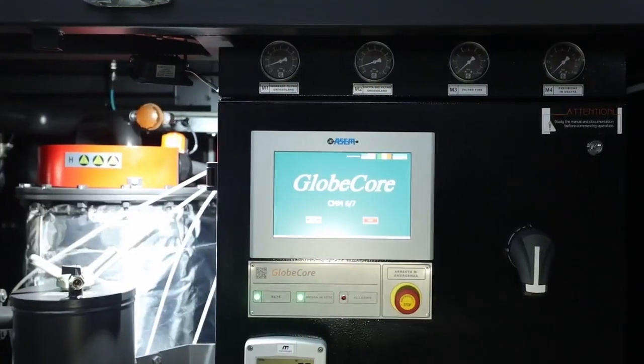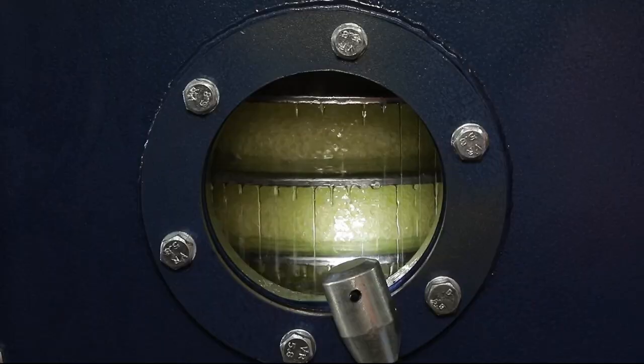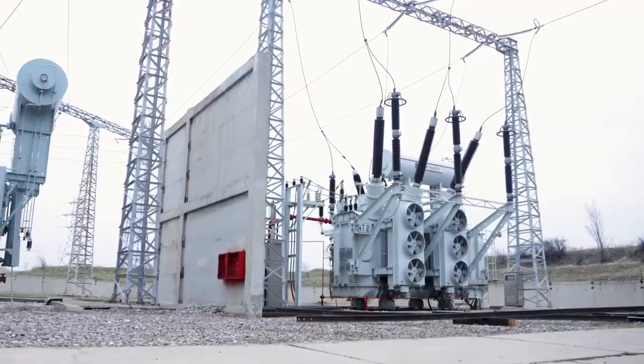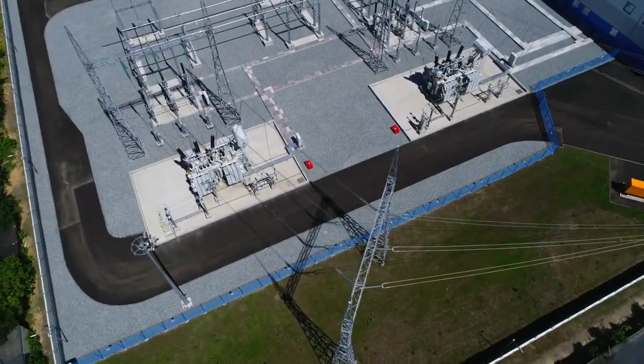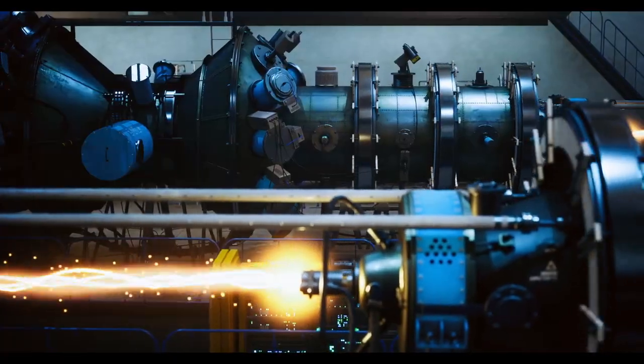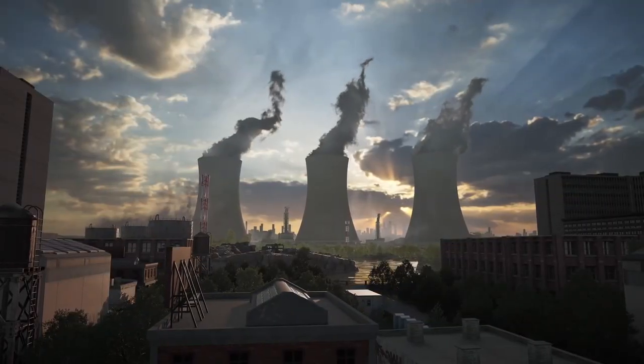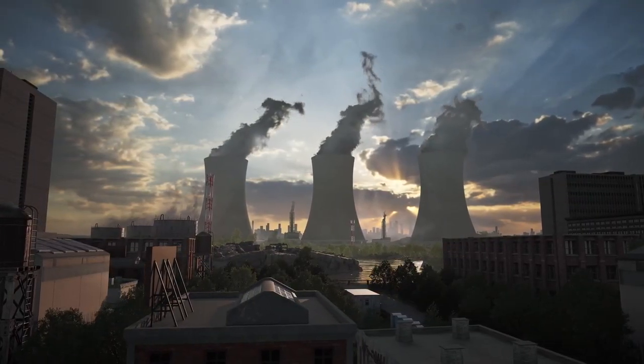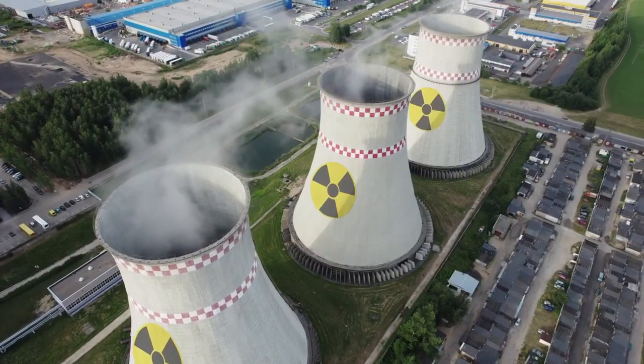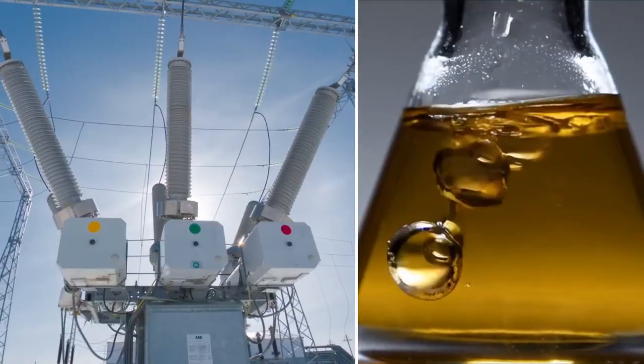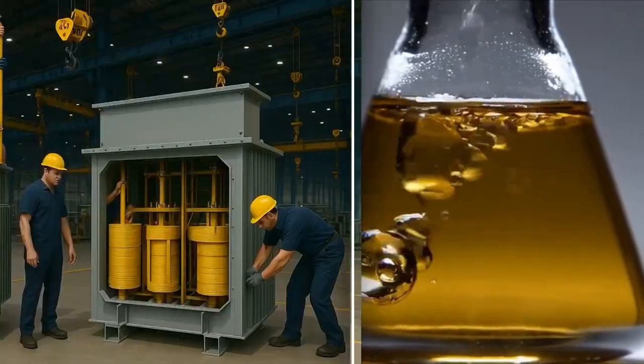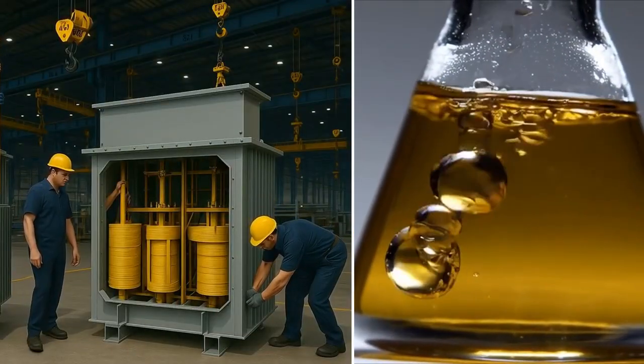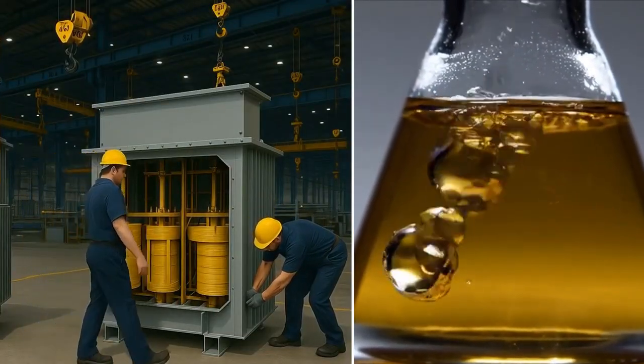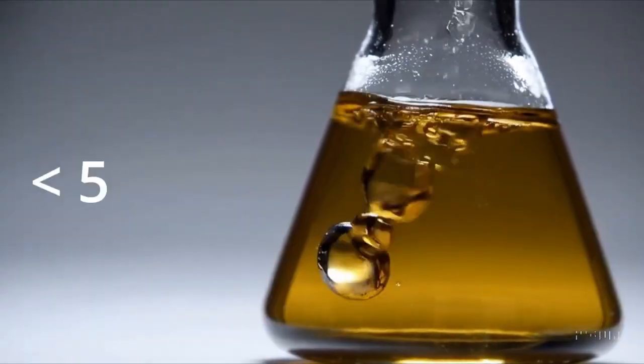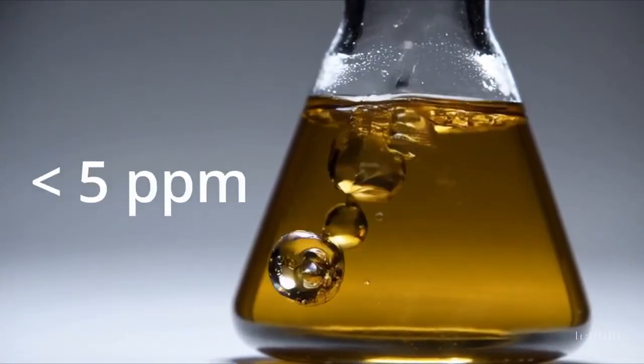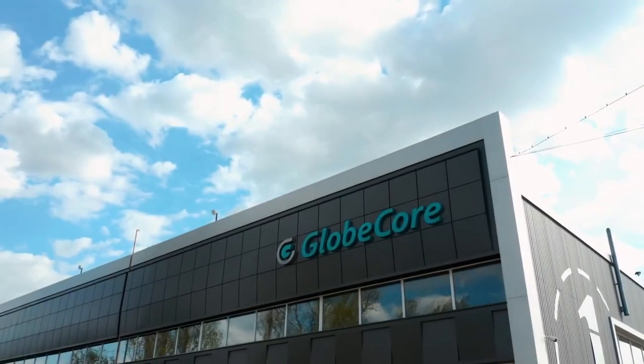However, some power-generating facilities have more stringent requirements for the moisture content of transformer oil. These include high-load transformers on the main power lines, and facilities with increased reliability requirements, such as nuclear power plants or military infrastructure facilities. Manufacturers of new transformers may also impose stricter requirements on the moisture content of transformer oil, striving for maximum oil purity prior to oil filling. In such cases, it is necessary to reduce the residual moisture to less than 5 parts per million.